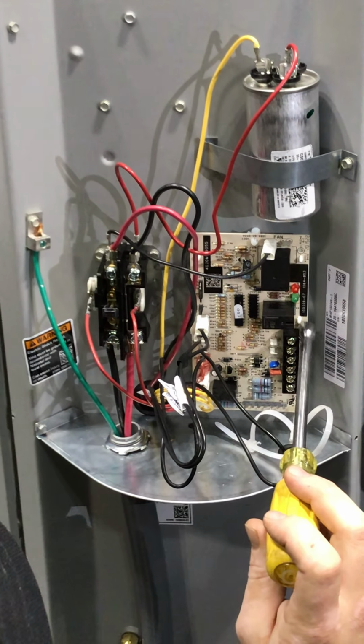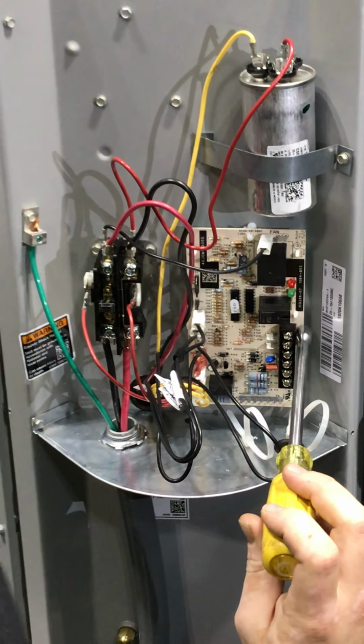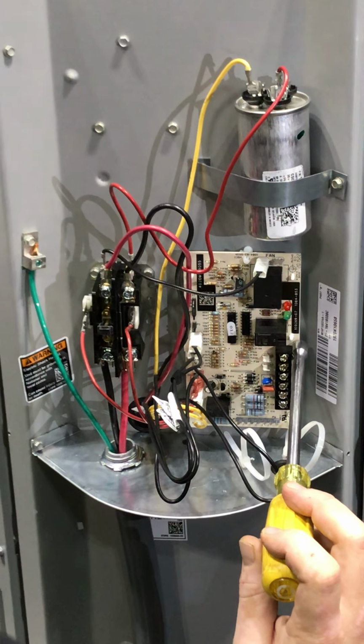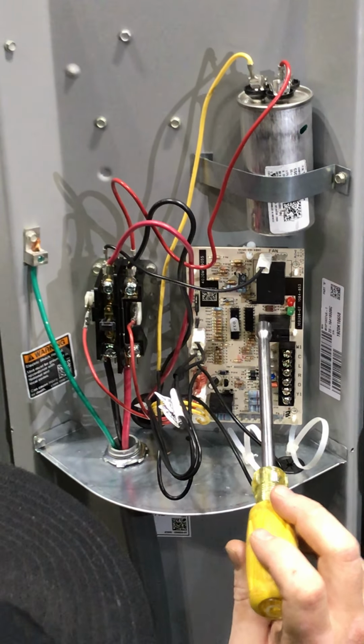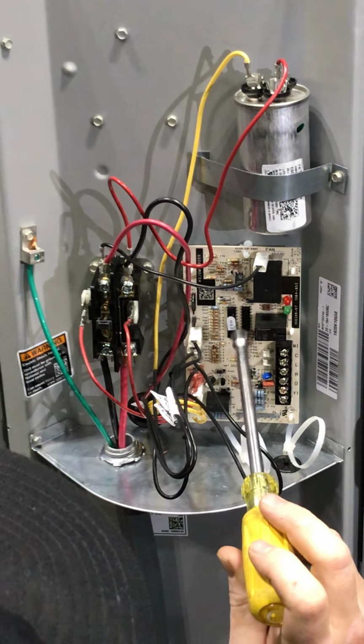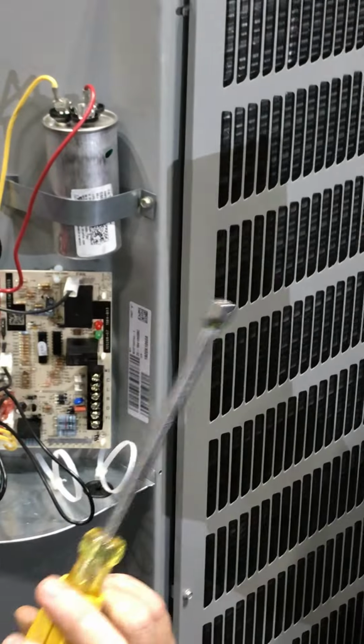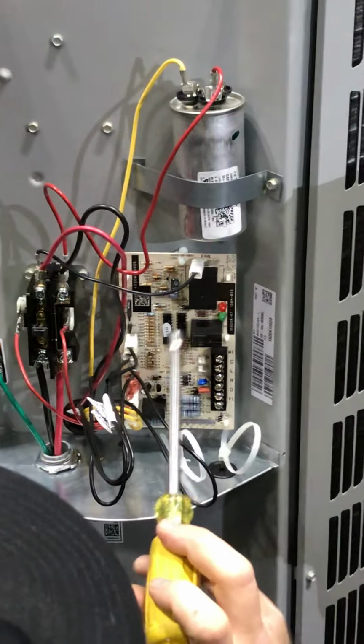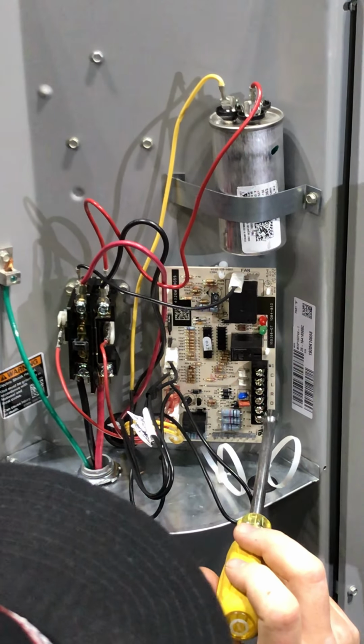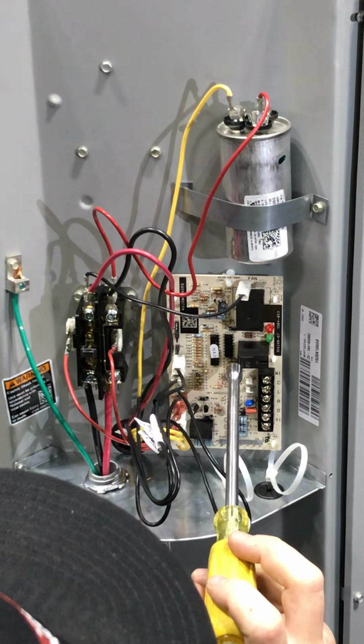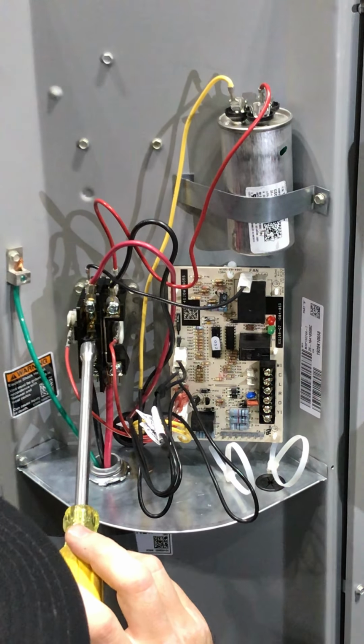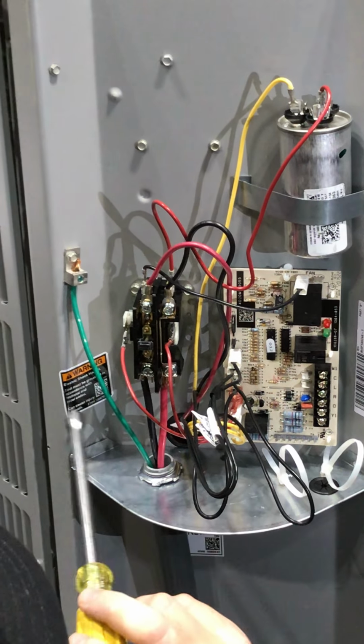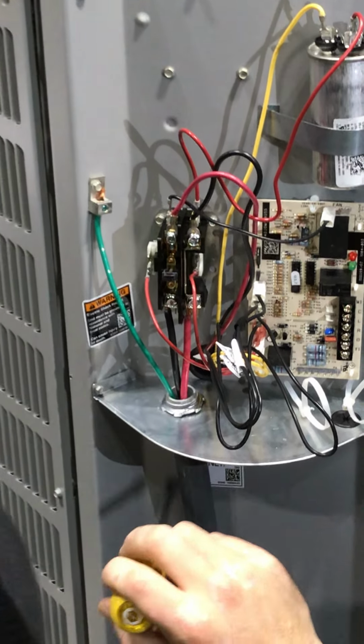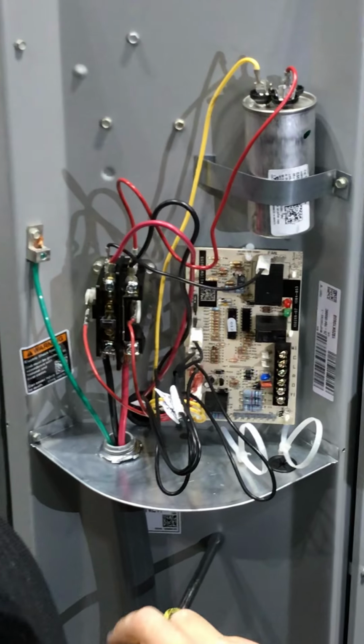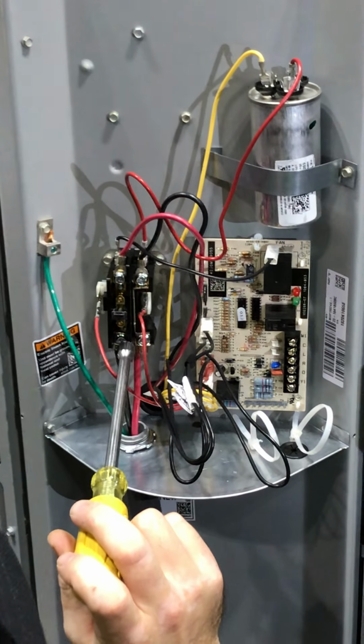Thermostat wire is going right here. You follow me, Richard? This is my defrost board. It's a control board. All right? It communicates with this unit and my thermostat to tell all the components what to do and when to do them. From here, I go to my contactor. My contactor is delivering my main power, which is coming from my whip here, to my fan and my compressor. It's being controlled from here.